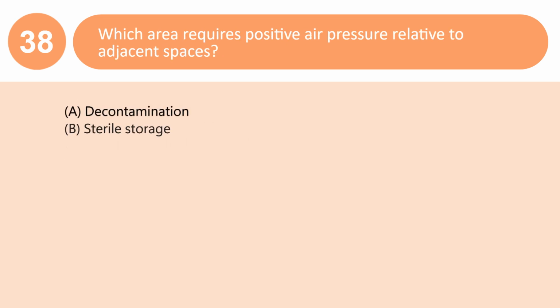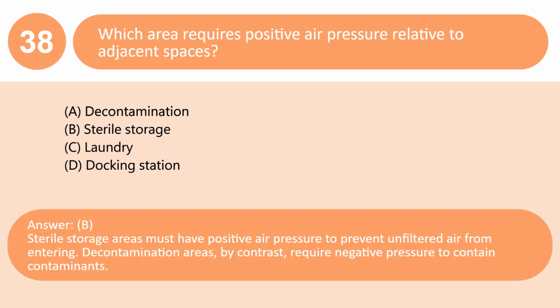Which area requires positive air pressure relative to adjacent spaces? A. Decontamination. B. Sterile storage. C. Laundry. D. Docking station. Answer: B. Sterile storage areas must have positive air pressure to prevent unfiltered air from entering. Decontamination areas, by contrast, require negative pressure to contain contaminants.